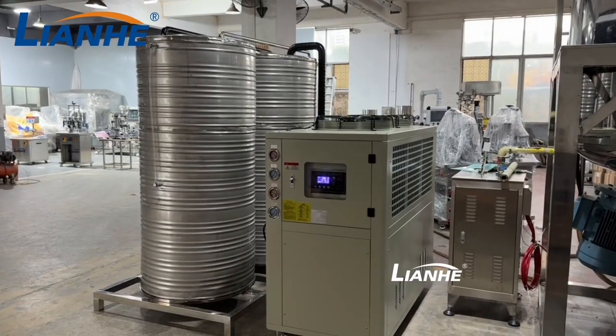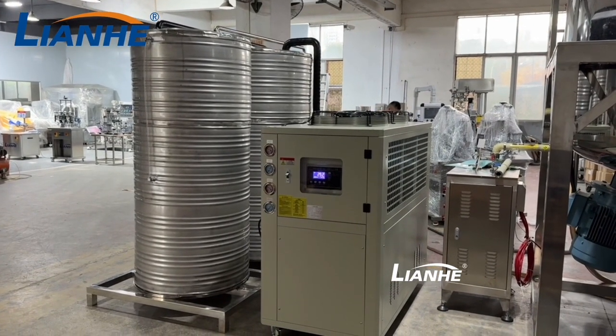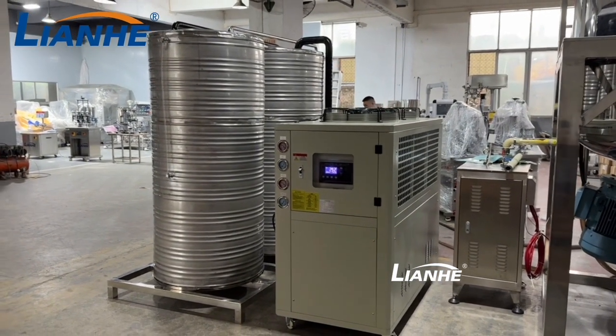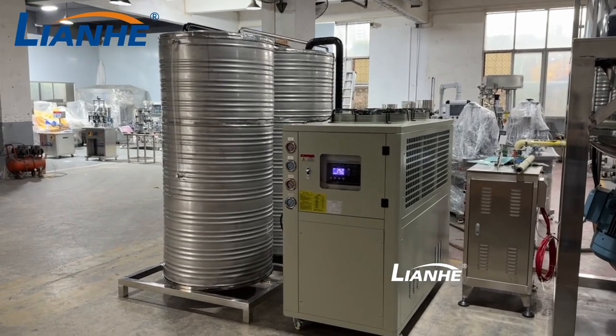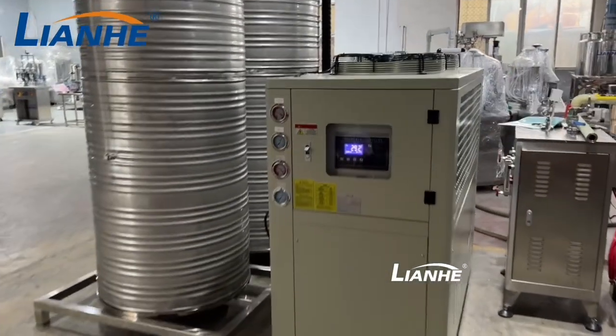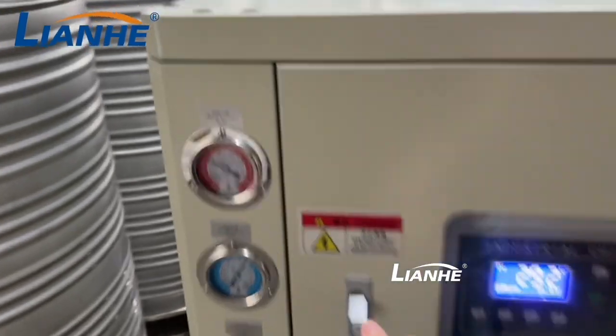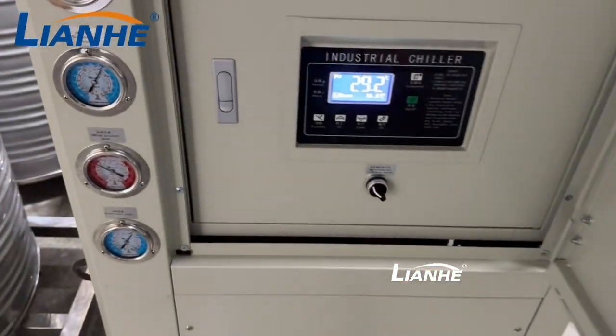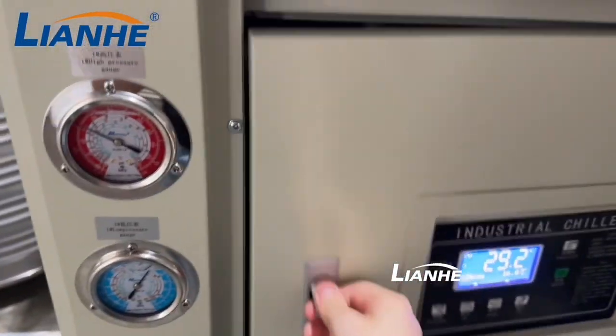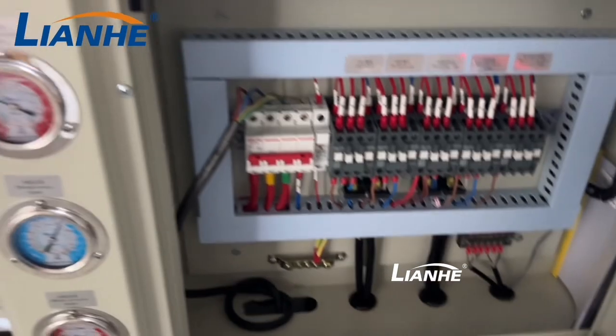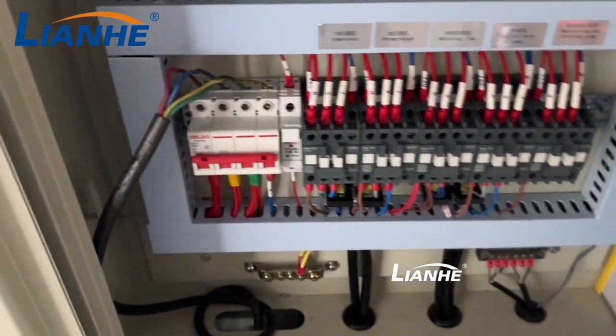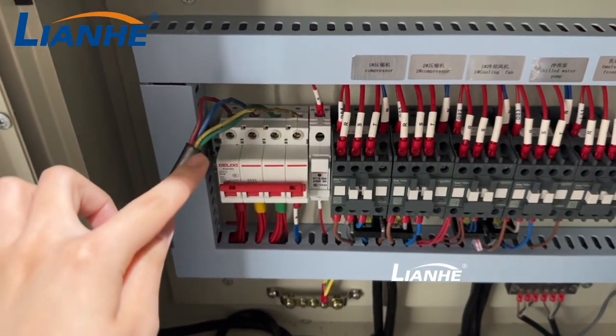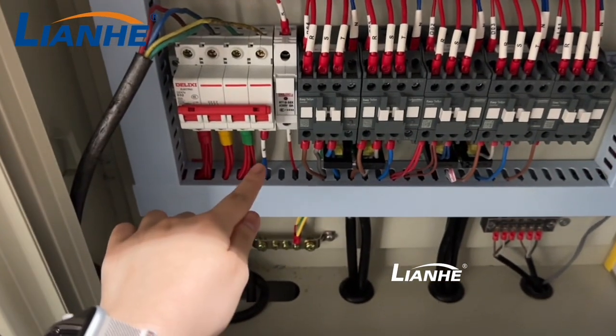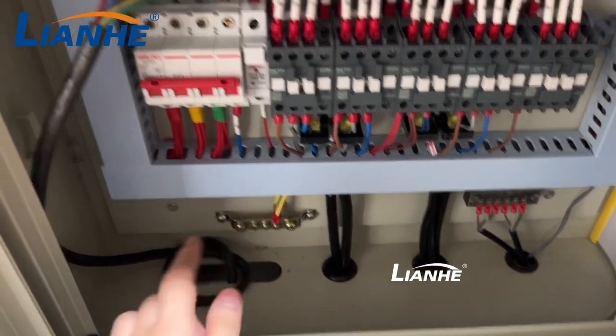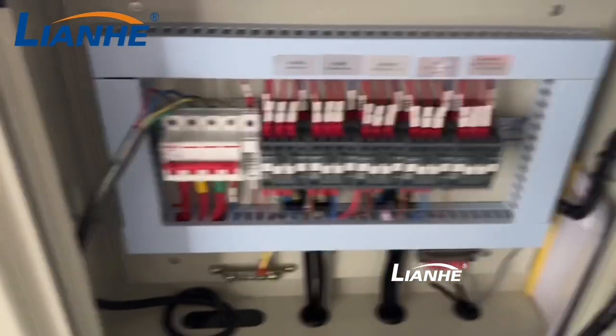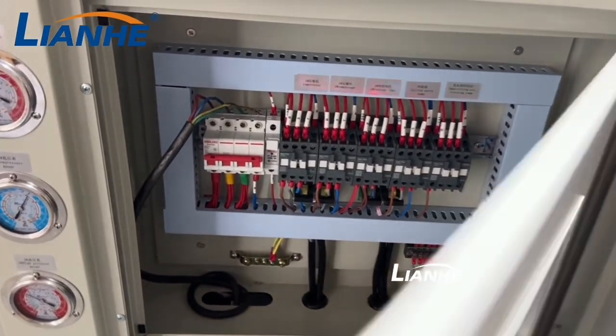Hello my friend, this is your 10 horsepower water chiller, and now I will tell you how to use this machine. First, when you receive this machine, you can open this, and now to connect to your power, here you can see the L1, L2, L3 wire, the neutral wire here, and the ground wire here. You should connect all these 5 wires to let the machine start to work.